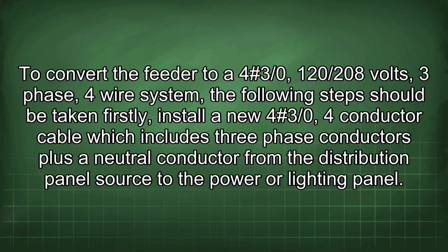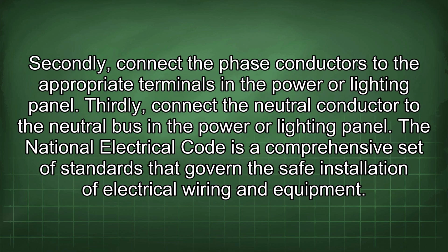To convert the feeder to a 4#3/0 120/208 volts 3-phase 4-wire system, the following steps should be taken. Firstly, install a new 4#3/0 4-conductor cable, which includes 3 phase conductors plus a neutral conductor, from the distribution panel source to the power or lighting panel. Secondly, connect the phase conductors to the appropriate terminals in the power or lighting panel. Thirdly, connect the neutral conductor to the neutral bus in the power or lighting panel.